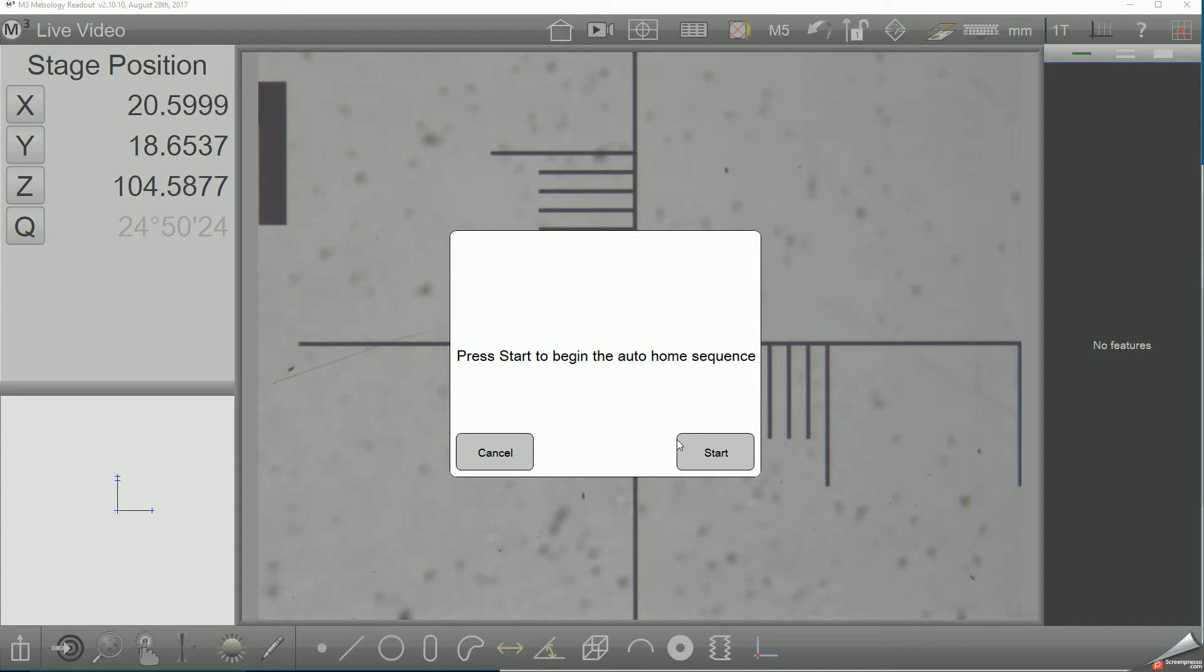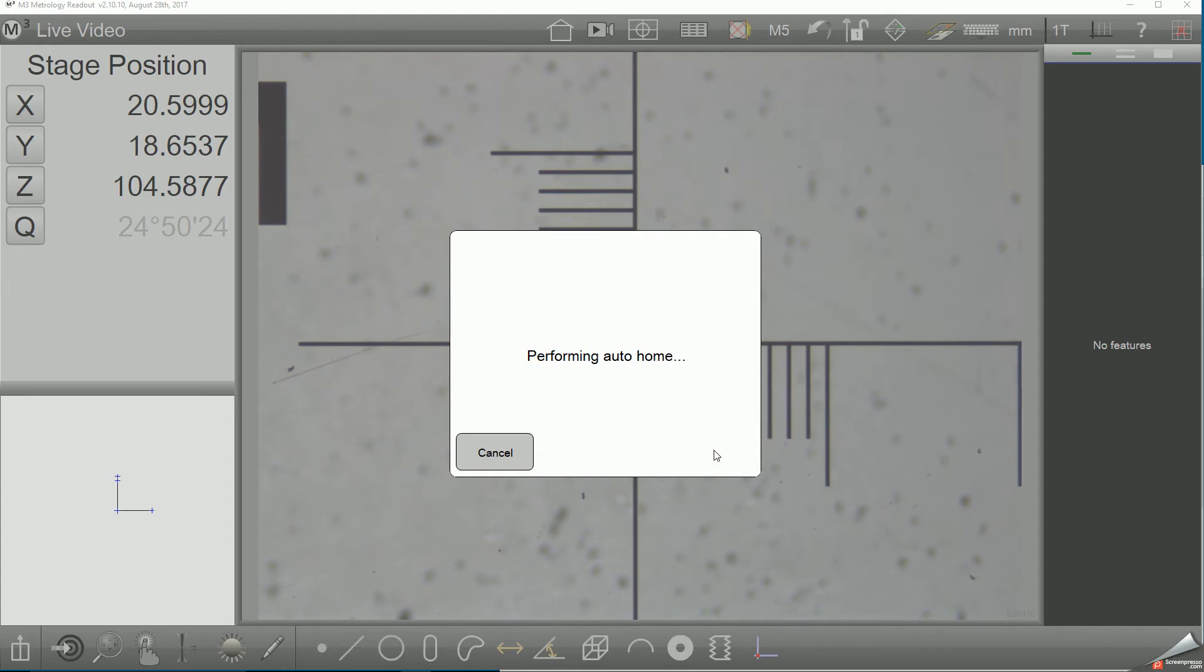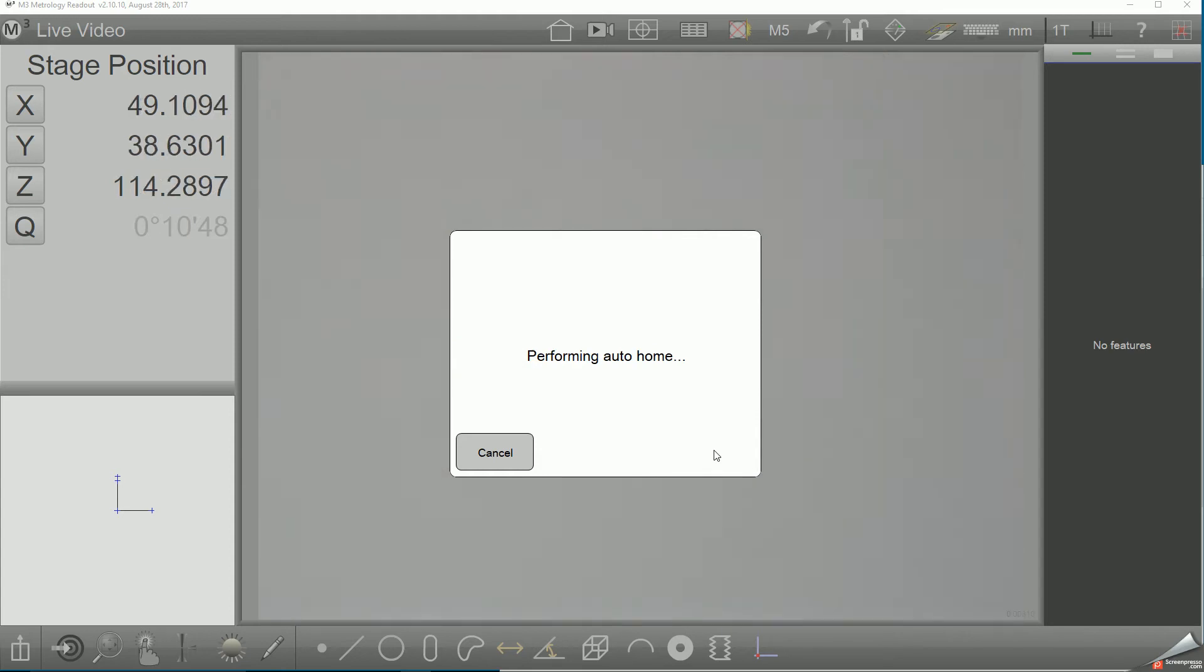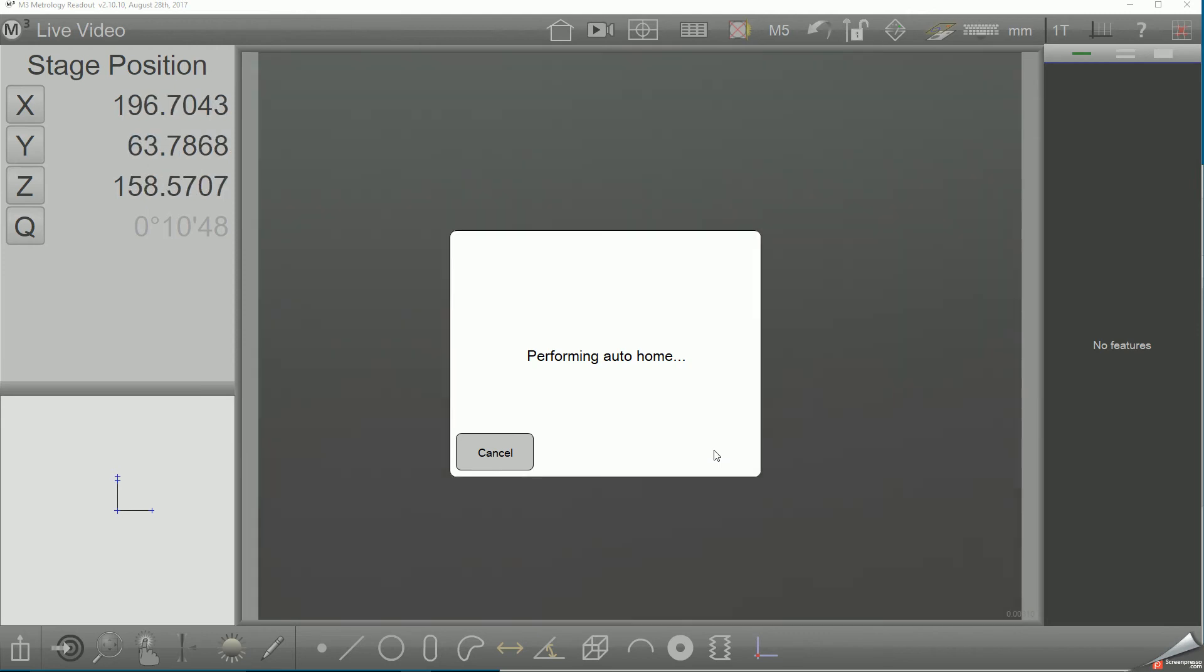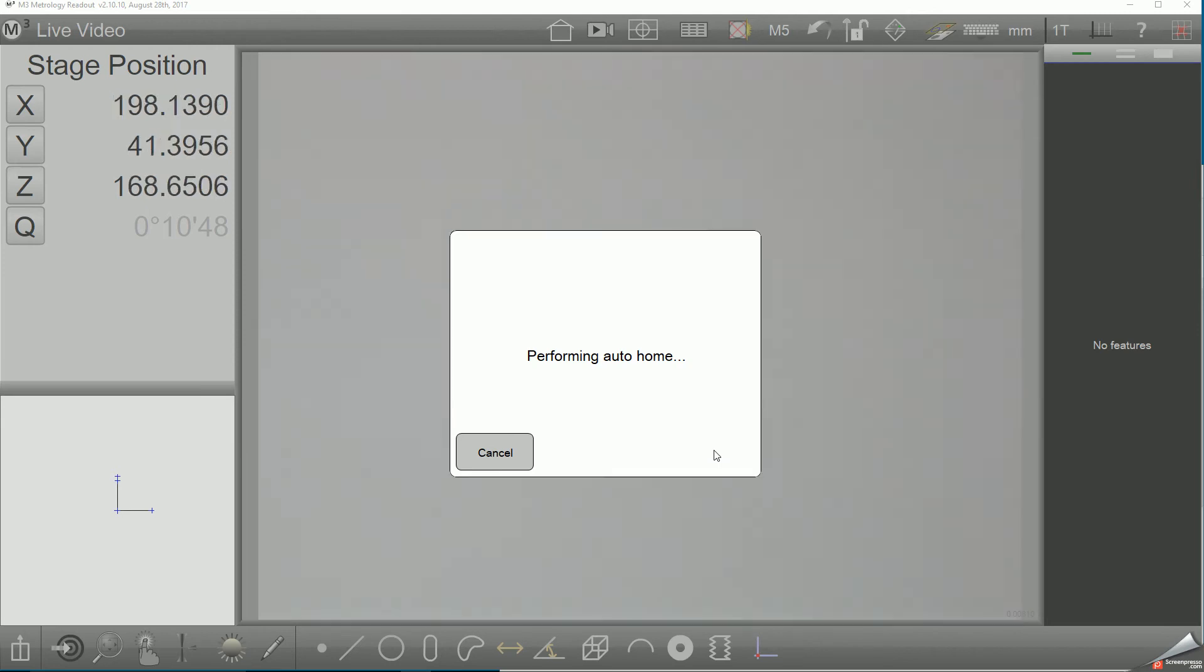SLEC is a segmented linear error correction method that requires a repeatable startup zero position in order to align the correction map each time the system is started up. As such, a repeatable zero position must be determined by the system by crossing the reference marks in the axes to be corrected.